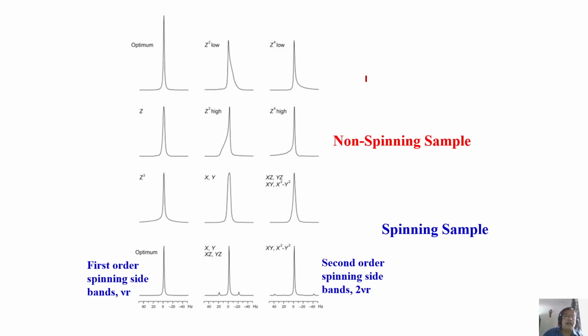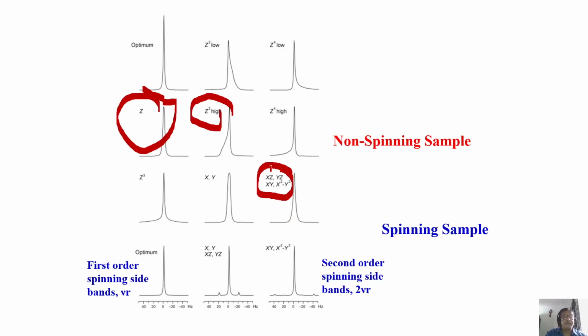In all the spectrometers, you have about 24 or sometimes 32 or 36 shim coils. There is a shim unit within the magnet. These are called room temperature shim coils, and there are about 36 of them. Some of them will vary the magnetic field gradient along the z-axis. By varying the current, you can create a counteracting field along the z-axis, sometimes along z squared, or an x and y combination. Varieties of things you can see.